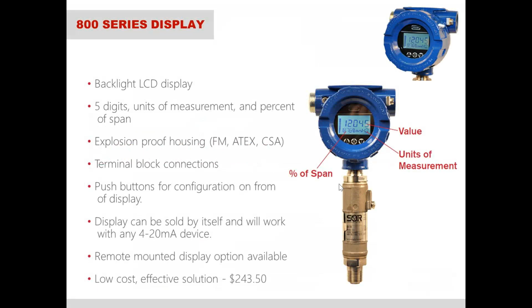The 815 and the 805 are what we call blind transmitters. They don't have a local indication as a standard. They just have flying leads that will then go to either an HMI screen or a DCS or a PLC somewhere where that signal will go and then be interpreted on a computer or program or some other type of method. Now, if local indication at the site of the transmitter or at the site of where the pressure is being taken is required, we can provide a local indicating display. So the option that we provide is a backlit LCD display, has 5 digits, displays units of measurement, and also displays the percent of span as well.